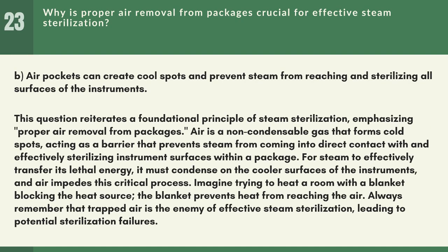Answer: B. Air pockets can create cool spots and prevent steam from reaching and sterilizing all surfaces of the instruments. This question reiterates a foundational principle of steam sterilization, emphasizing proper air removal from packages. Air is a non-condensable gas that forms cold spots, acting as a barrier that prevents steam from coming into direct contact with and effectively sterilizing instrument surfaces within a package.